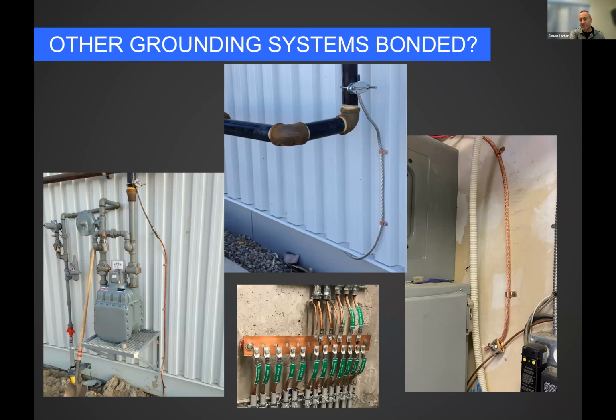If we must bond something with cathodic protection, there are other options. We wouldn't be using a listed fitting like that. We would use something like a spark gap bonding connection. I've never used one, so I suspect you will never see one. It's just an option. But if you do inspect a system where you see something a little odd about the gas pipe bond, talk to the installer. They may have had to use a spark gap. I doubt you will ever have to, though.